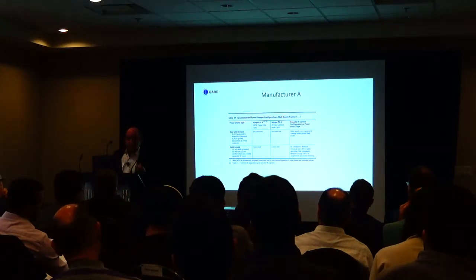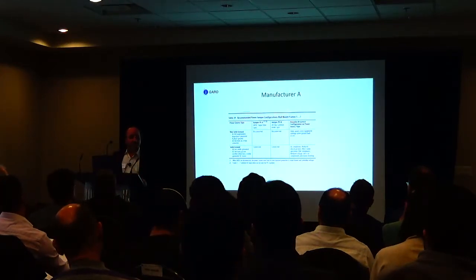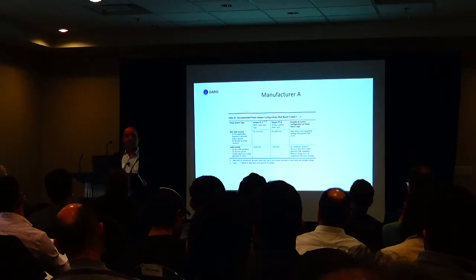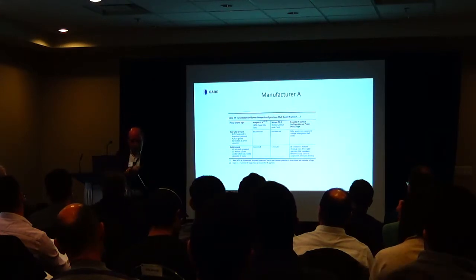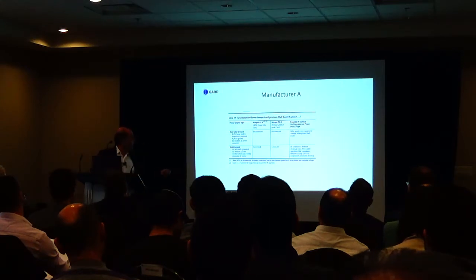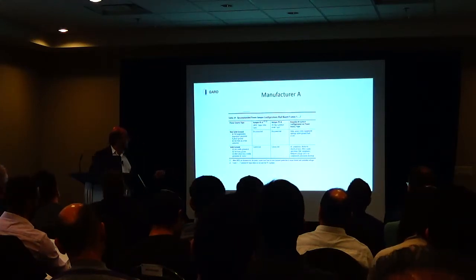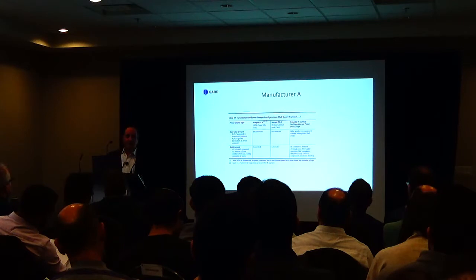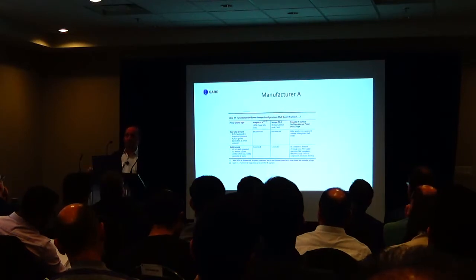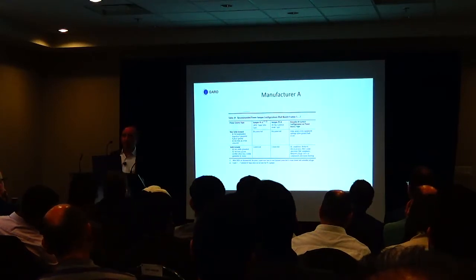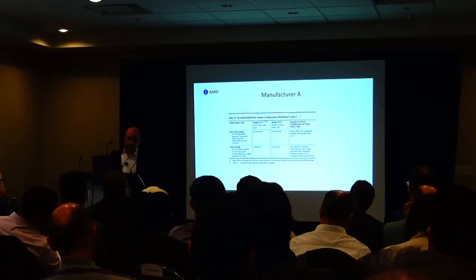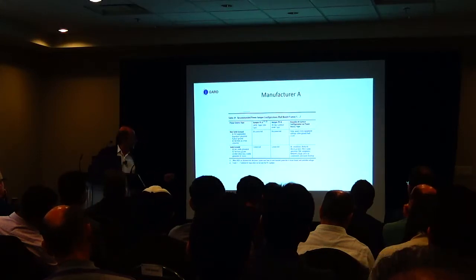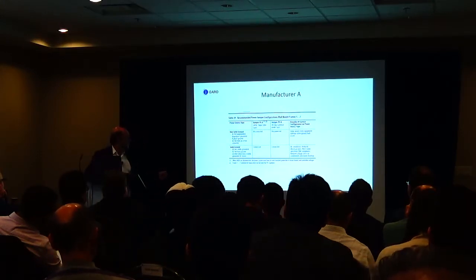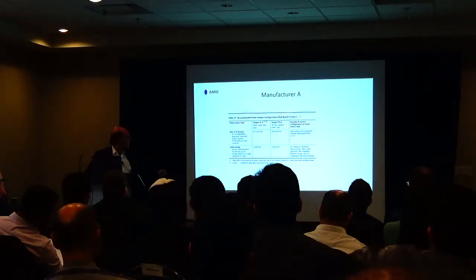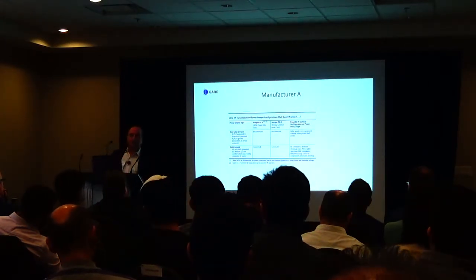So we have issues sometimes with variable frequency drives. I'm going to try to do this quickly too because... So here's one manufacturer who says that there's 2 jumpers that have to be made. You have to alter these 2 jumpers in order to make the drive compatible with a resistance grounded system. Okay? You have to disconnect it here and disconnect it here for basically these types of systems, non-solidly grounded systems.